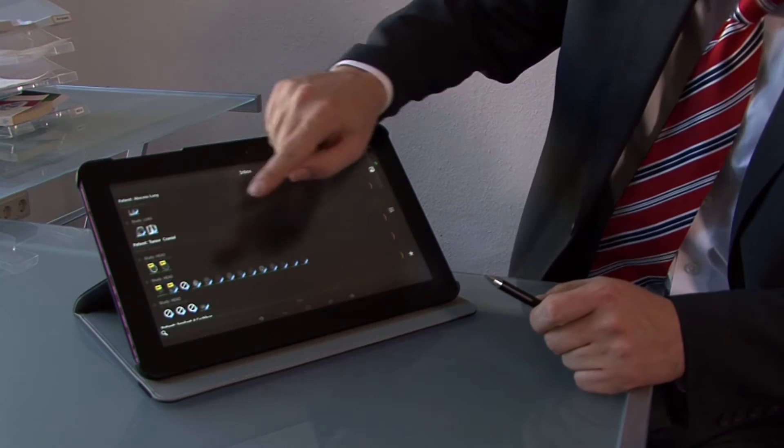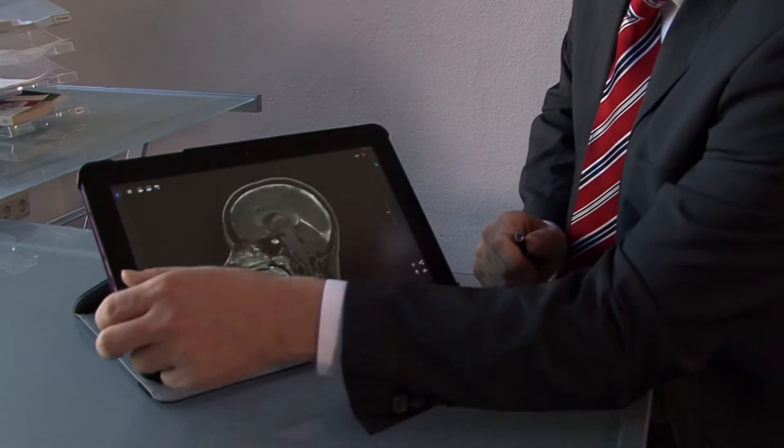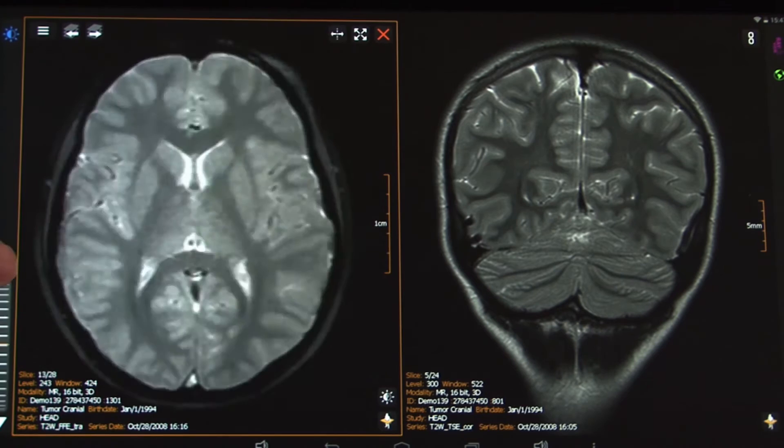Medical display requirements are different from country to country, but they are very similar. Typical requirements are that you need a homogeneous visualization. Consumer displays come with a deviation of more than 50%, but medical displays need to be homogeneous. There should be a so-called minimum pixel size, so pixels should have a minimum size in order to have a good angle for the human eye to see it. Grayscale calibration should deviate a maximum of 10% from the proper linear curve.